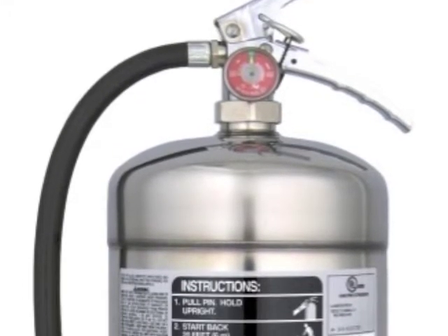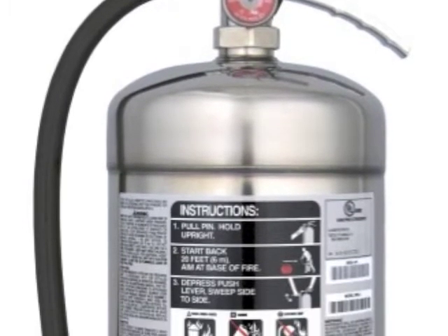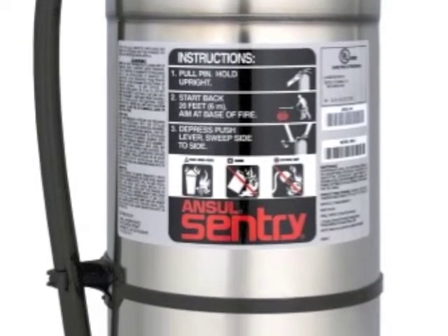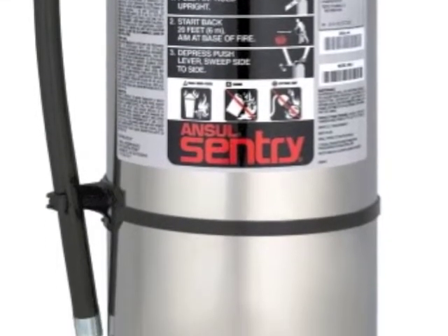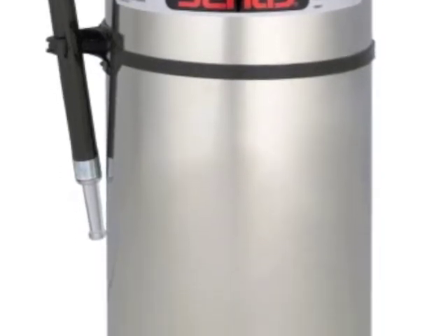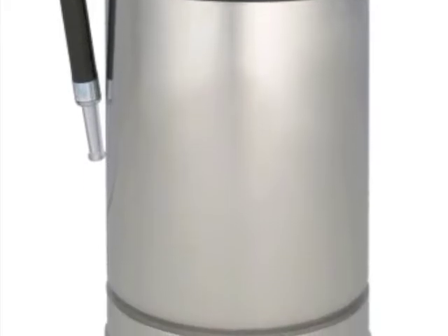Water and foam fire extinguishers extinguish the fire by taking away the heat element of the fire triangle. Water extinguishers are only used for Class A fires. They should not be used on Class B or C fires. The discharge stream could separate the flammable liquid in a Class B fire or could create a shock hazard in a Class C fire.